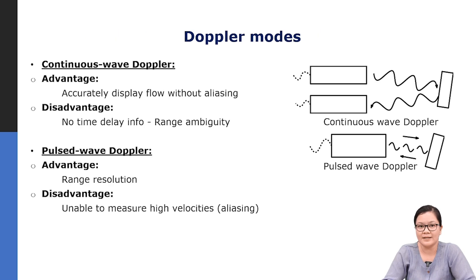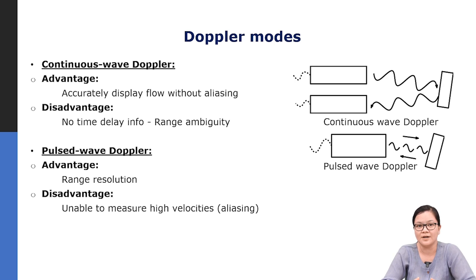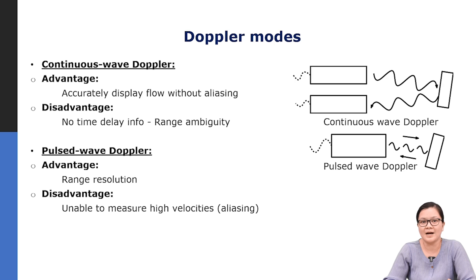The advantage of continuous wave Doppler is that it can accurately display flow without aliasing. A disadvantage is that, with continuous wave signals, there is no time delay information, making it challenging to determine the range location of what is being imaged. The advantage of pulsed wave Doppler is better range resolution using time delay information. A disadvantage is the inability to measure high velocities due to aliasing, which will be discussed in a subsequent lecture.